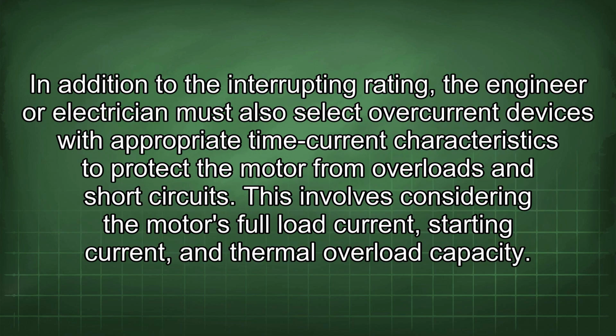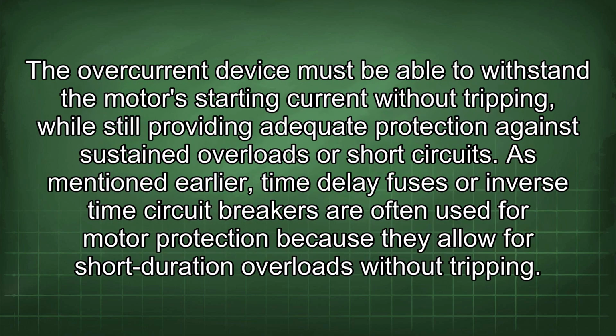In addition to the interrupting rating, the engineer or electrician must also select overcurrent devices with appropriate time current characteristics to protect the motor from overloads and short circuits. This involves considering the motor's full load current, starting current, and thermal overload capacity. The overcurrent device must be able to withstand the motor's starting current without tripping, while still providing adequate protection against sustained overloads or short circuits.